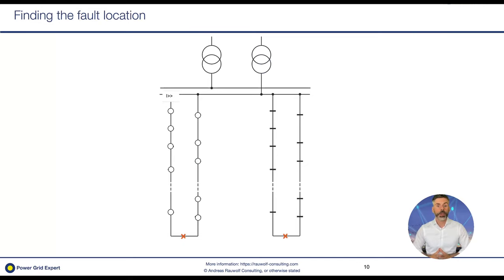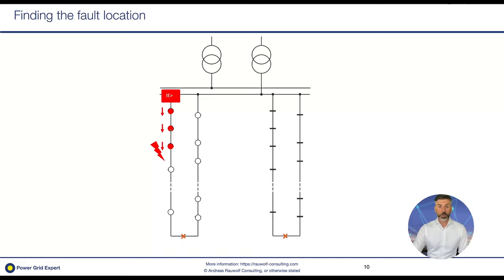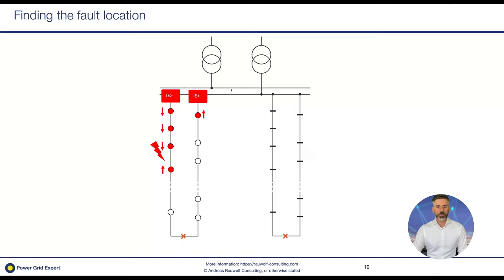In case of a fault, we have our feeder with a normally open point, and the fault location is between two secondary substations. The protection relay in the fault feeder indicates an earth fault pointing toward the feeder. The indicators present will point toward the fault location. It can also happen that there is an indication behind the fault location, but it still points toward the fault location. In healthy parts of the feeder or in totally different areas, backward indications may occur — but once you know this, you can filter them out easily.